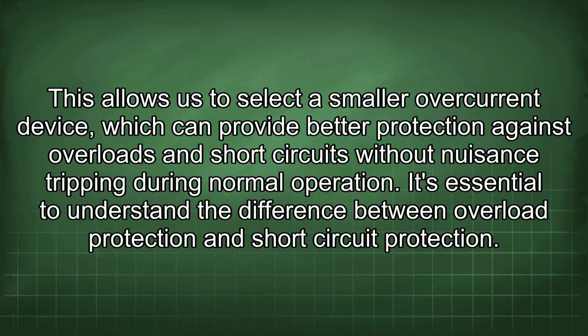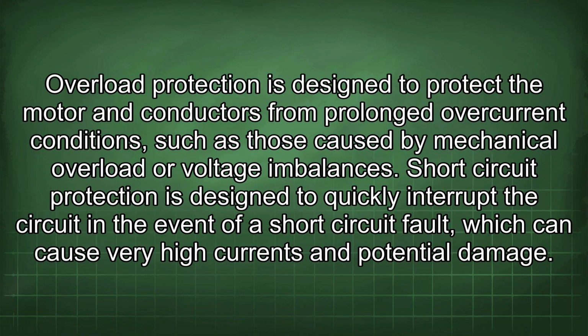This allows us to select a smaller overcurrent device, which can provide better protection against overloads and short circuits without nuisance tripping during normal operation. It's essential to understand the difference between overload protection and short circuit protection. Overload protection is designed to protect the motor and conductors from prolonged overcurrent conditions, such as those caused by mechanical overload or voltage imbalances. Short circuit protection is designed to quickly interrupt the circuit in the event of a short circuit fault, which can cause very high currents and potential damage.